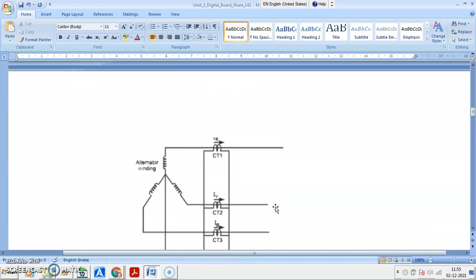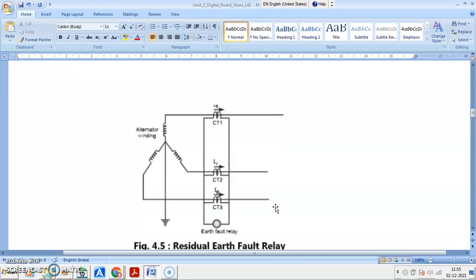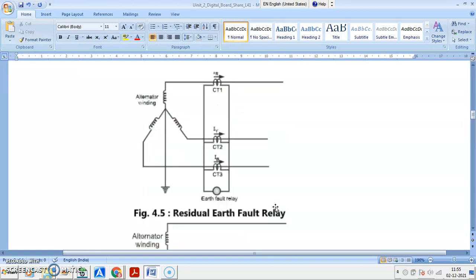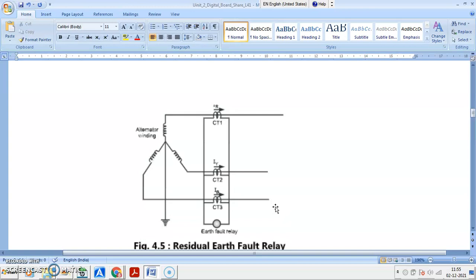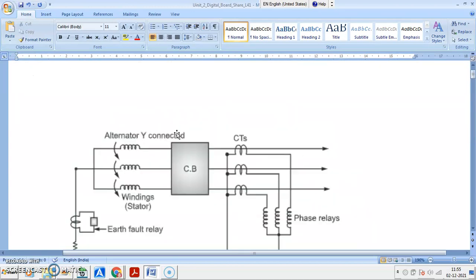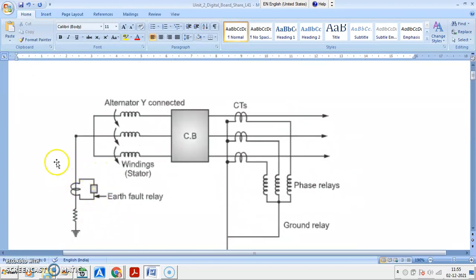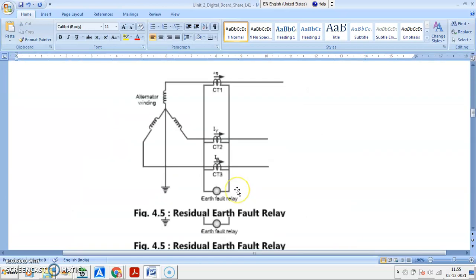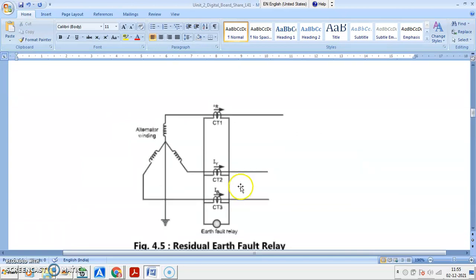Then earth fault protection of alternator. Residual earth fault relay, it is shown over here. Earth fault protection of alternator, here it is mentioned. This is earth fault relay. So this is earth fault protection of alternator, diagram of residual earth fault relay. This is alternator winding, star connected, neutral point grounded. Any doubt?